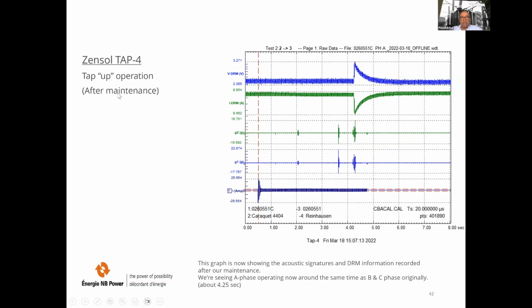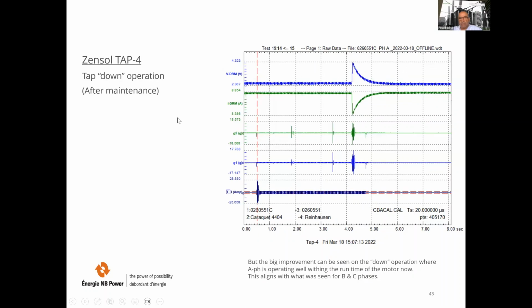Here, tap up after maintenance. This graph is now showing the acoustic signatures and DRM information recorded after our maintenance. We're seeing A phase operating now around the same time as B and C phase originally, about 4.25 seconds. So you see now we're not at this impact, we're here. Tap down: the big improvement can be seen on the down operation, where A phase is operating well within the runtime of the motor now. Like in the previous, this was happening at the end of the motor current, and now this aligns with what was seen for B and C phases.